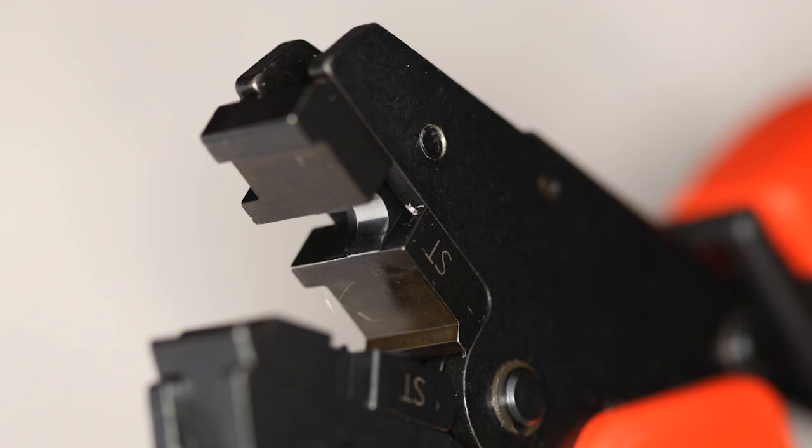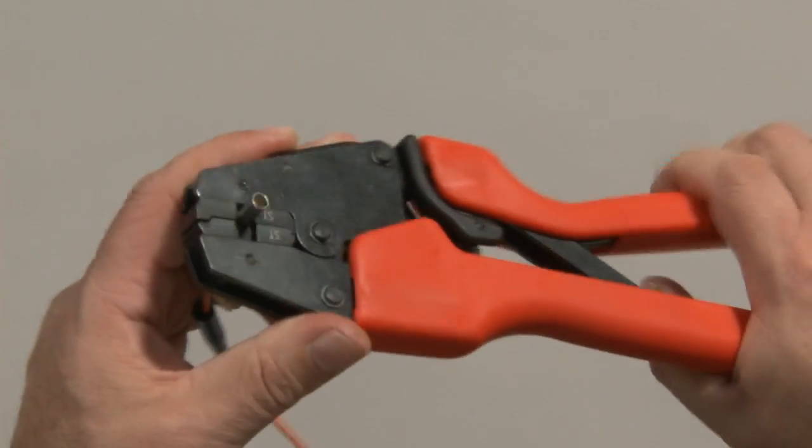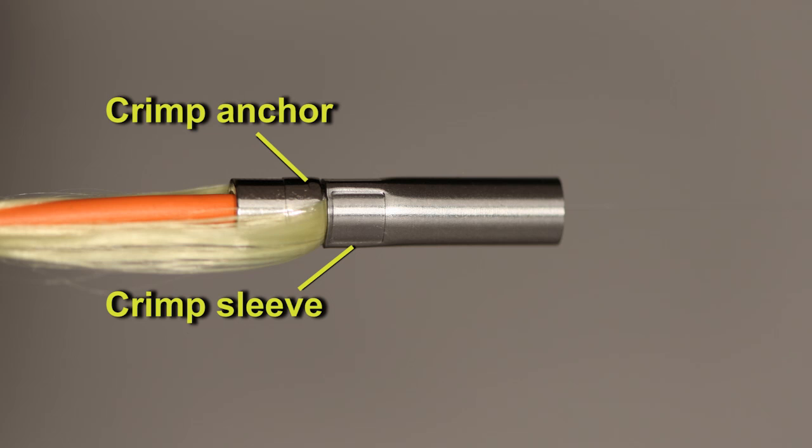Position the crimp sleeve in the tool so that the back edge of the sleeve is aligned with the crimp nest. Squeeze the handles until you hear a click. This will leave a depression on the crimp sleeve where it is crimped to the crimp anchor.